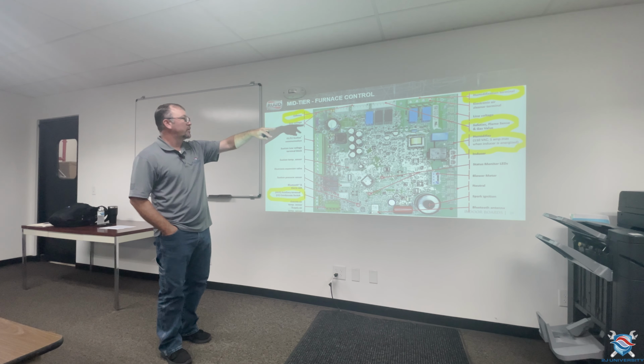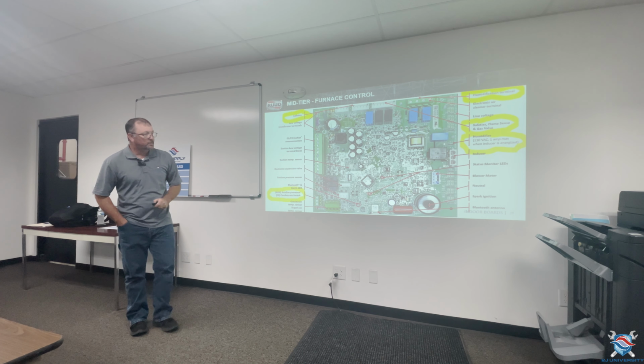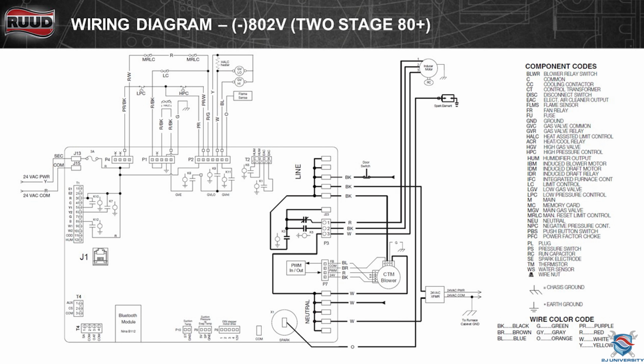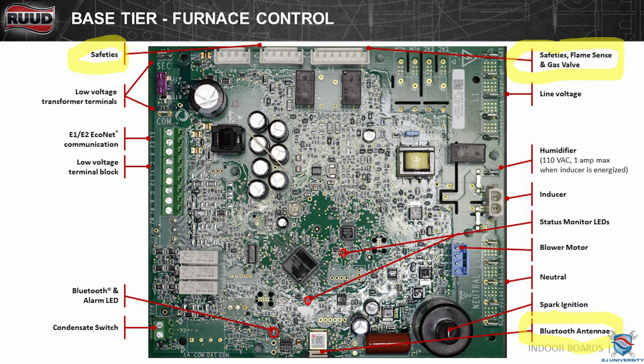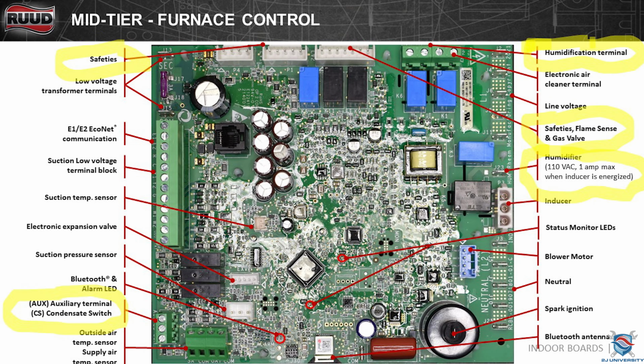Safeties and flame sensor, I just wanted to point that out again. Talked about that. Same thing, wiring diagram, gas valves, high and low. So like on this board, we looked at it, the dry contacts aren't on this board. You have a regular 110 volt humidifier, but on this board you have both. That's kind of what I was talking about. I only point that out because I get that question all the time: is my humidifier powered, or is it dry contacts off the board?